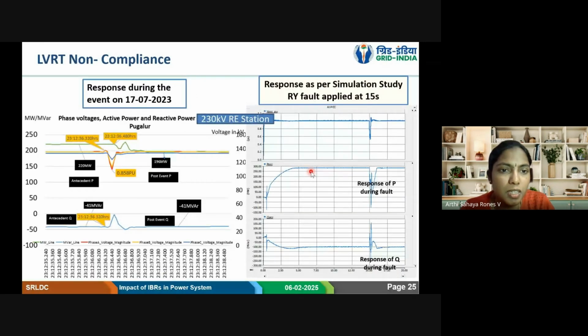Then one another case happened in a station near Pugalur. Here also there was a fault in a 400 kV Pugalur connected line, and it was an RY fault. One more thing: most of the time, when there are phase-to-phase faults, we see IBRs get tripped based on the severity of the phase-to-phase fault. Usually for phase-to-ground faults in the grid end, we have not observed major tripping of IBR. During phase-to-phase faults, many trippings are there.